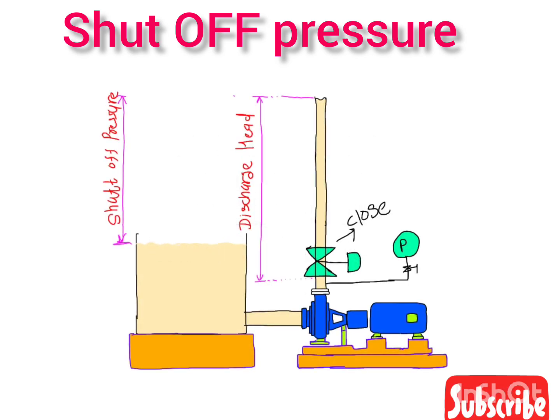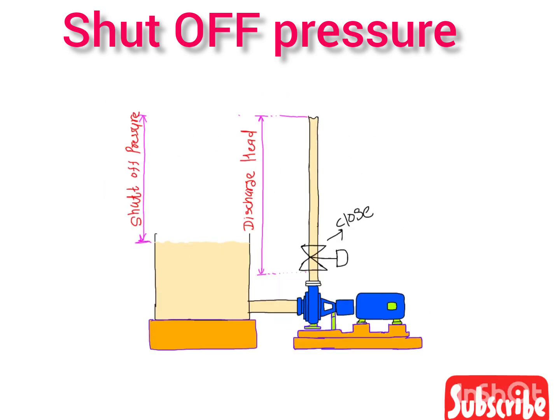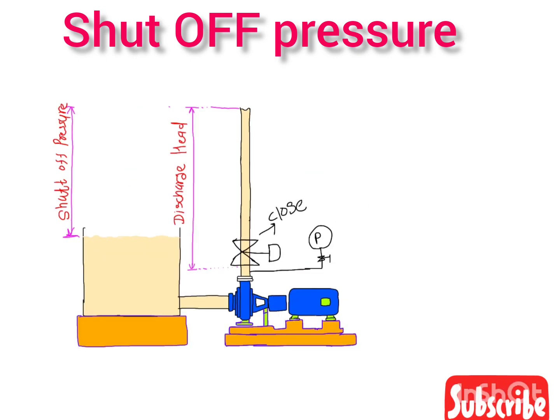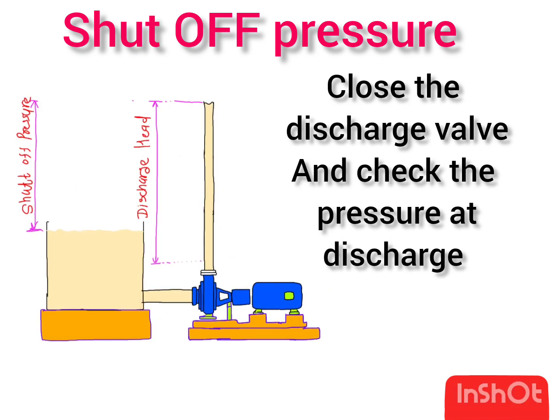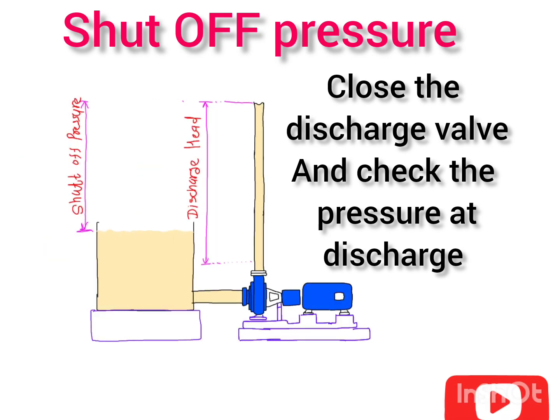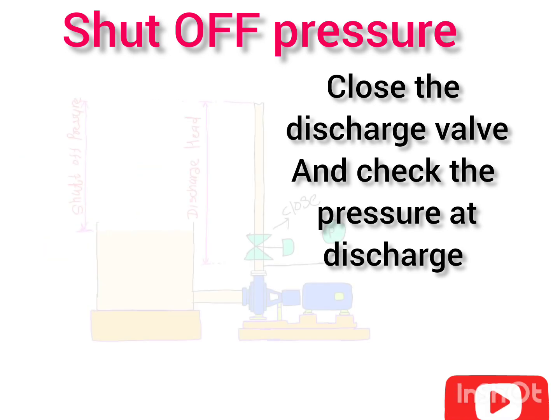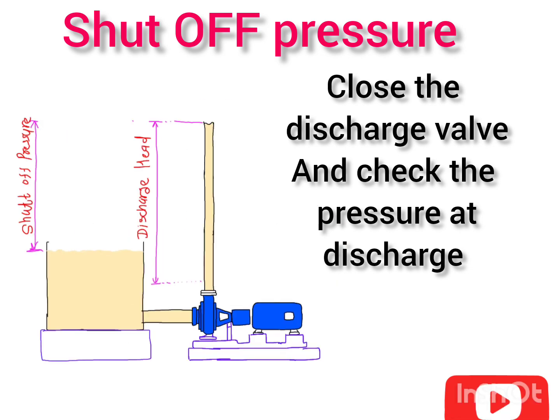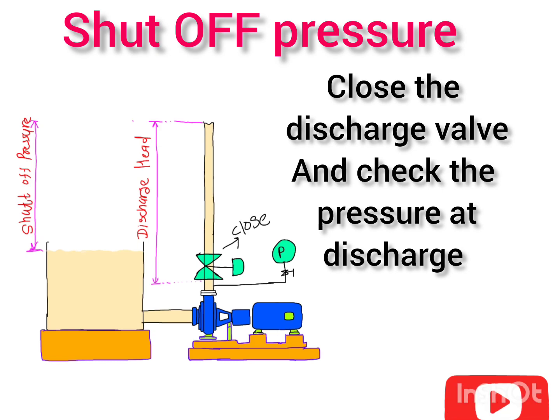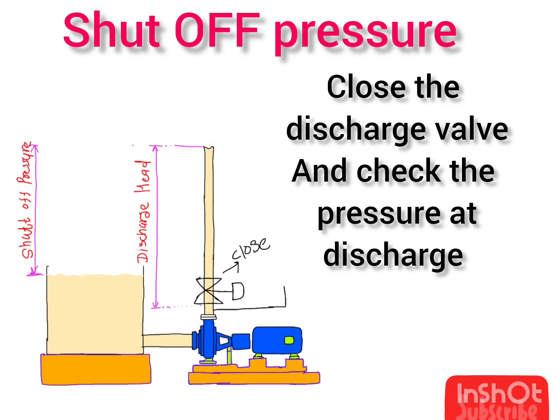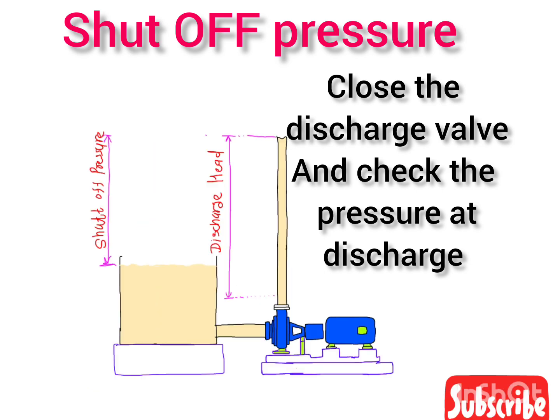If you want to know what is the shut-off pressure in your centrifugal pump, just close the outlet discharge valve of the centrifugal pump and see what is the maximum pressure that the pump generates on the discharge side. That maximum pressure on the discharge side is nothing but your shut-off pressure.